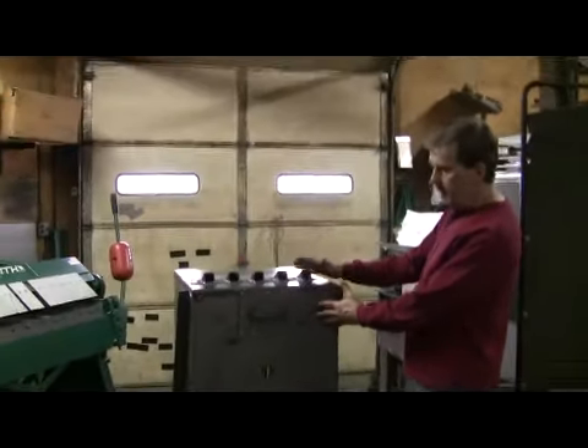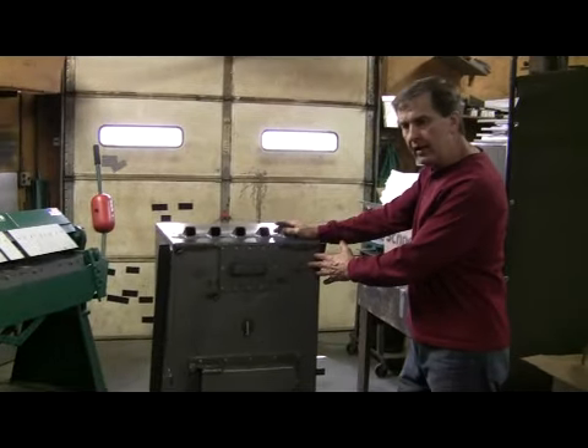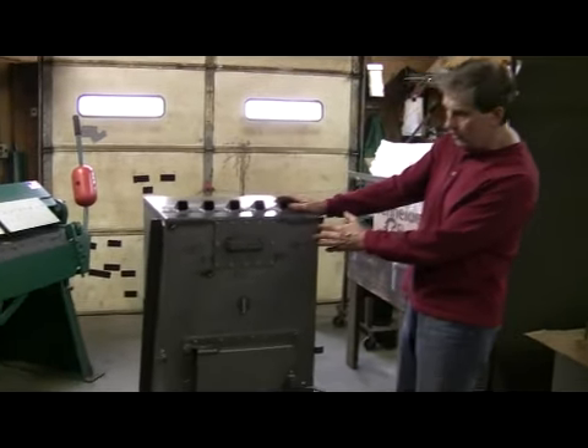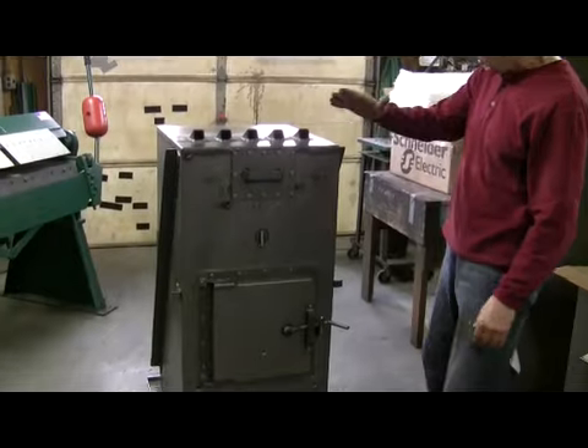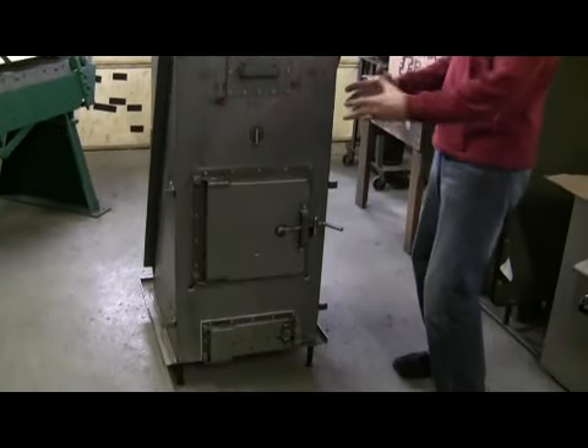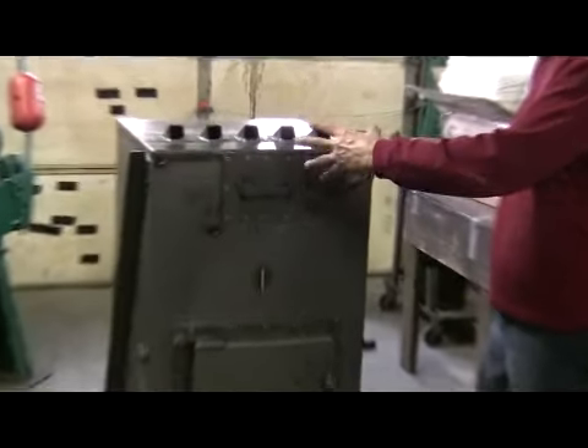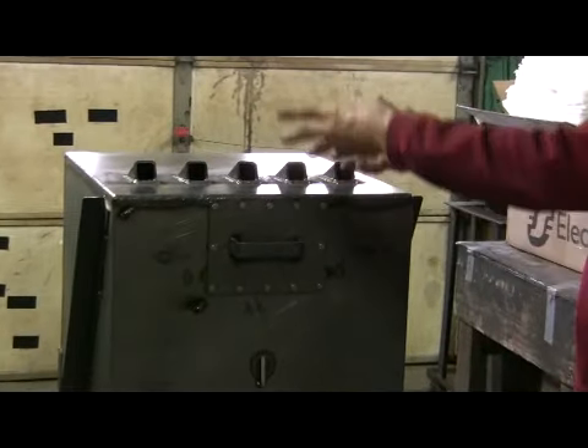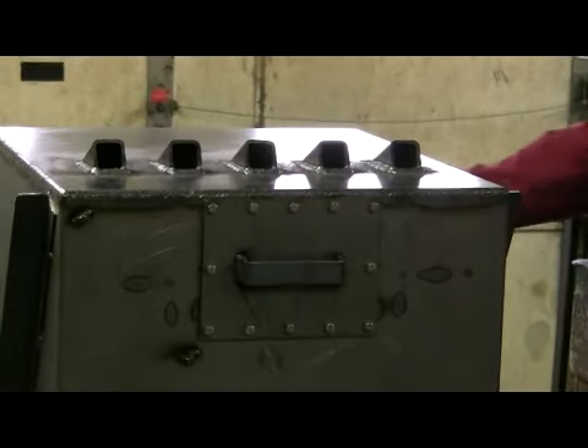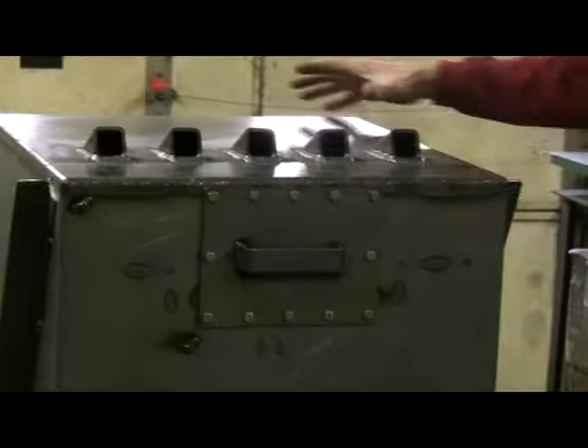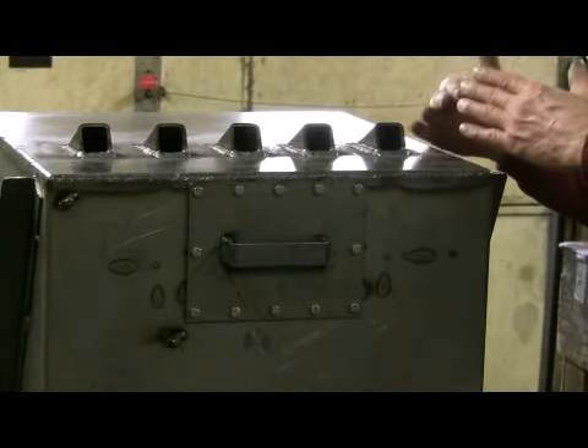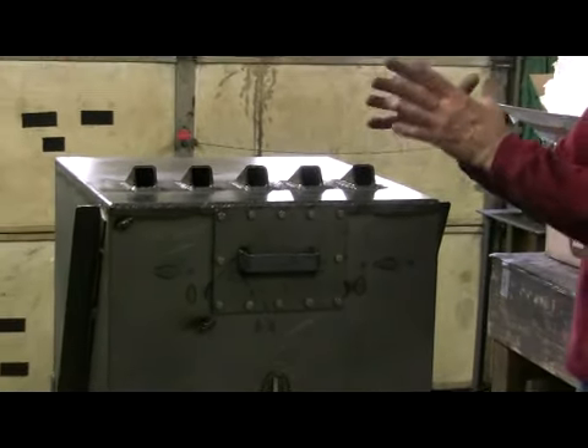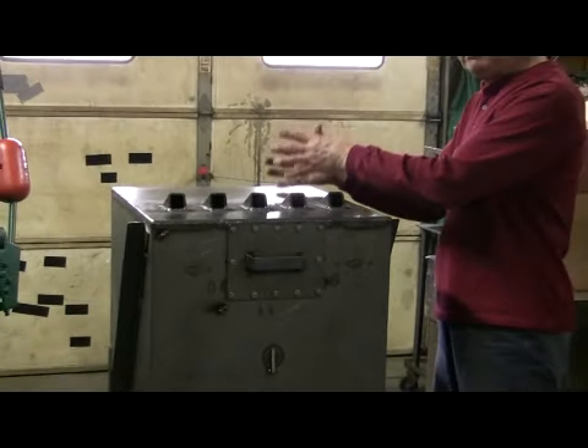Okay. This right here would be a vapor fire furnace that does not have the air jacket on it yet. I wanted to show you the way the heat exchanger tubes go through the heat exchanger at an angle, so when the furnace is burning complete and all the gases are being burned and they go up into the heat exchanger, your fan blows air around the furnace and then also through these tubes that are at an angle through the heat exchanger to extract the heat so you do not waste a lot of heat up the chimney.